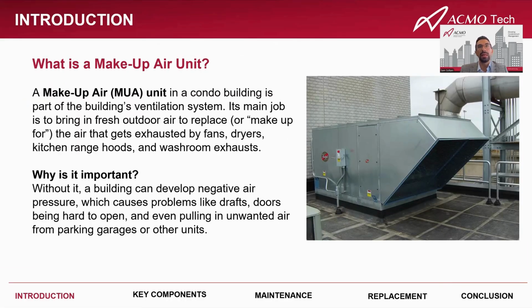A makeup air unit is a part of the condo's ventilation system. Its job is simple. It brings in outdoor fresh air to replace the air that's being exhausted by fans, dryers, and kitchen range hoods. Without it, the building ends up under negative pressure. And this leads to doors being hard to open, drafts, which result in stack effect, and even unwanted air being pulled in from parking garages or odor migration from one suite to another.